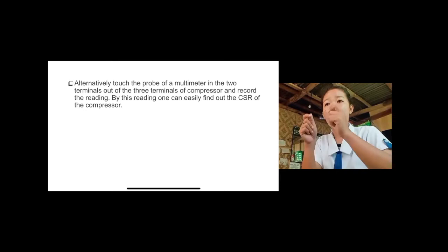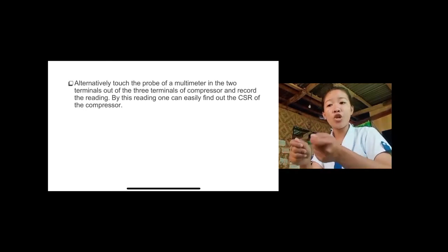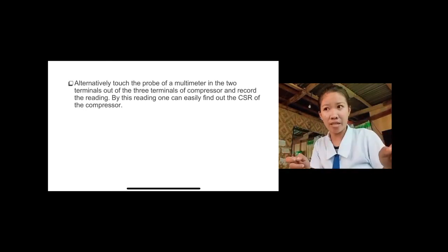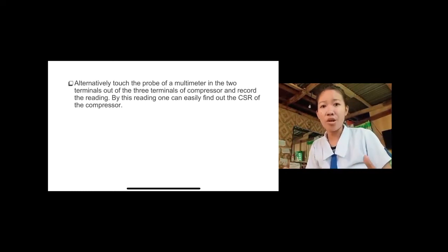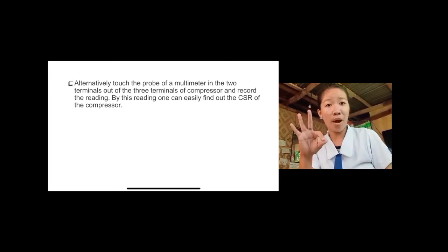At every terminal pair you should record the readings. This way we can easily find out the CSR of the compressor. The highest reading will be the start winding. There are three terminals of the compressor. When you are done recording the readings of the three terminals, you should identify which has the highest reading.